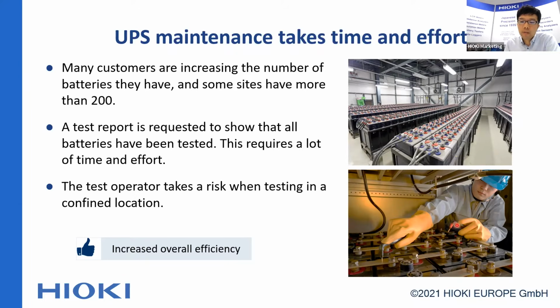However, for the test operator, as you can see in this picture, sometimes batteries are located at the backside of shelves. In this case, it is difficult to access the battery terminals. Also, the UPS has high voltage, so the test operator has a risk of electrical shock during the test.